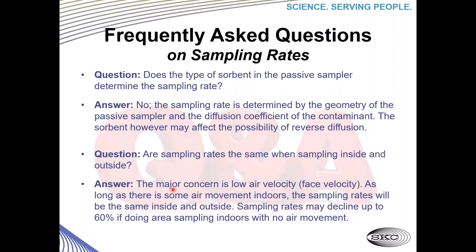Another popular question: are sampling rates the same when sampling inside and outside? The major concern is low air velocity or face velocity. As long as there is some air movement indoors, the sampling rates will be the same inside and outside. But sampling rates may decline up to 60% if doing air sampling indoors with no air movement.